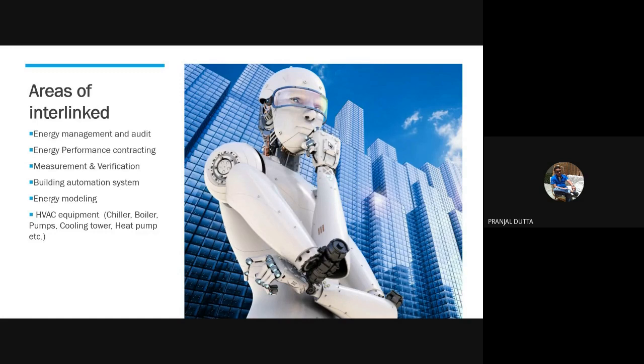That needs to be verified by someone M&V certified. Building automation is also very essential, because the entire software runs on data taken from the existing BMS—data for chillers, pumps, cooling towers, user sites, room temperature set points, flow, pressure, temperature, all coming from the building automation system. You need a fair idea of how equipment is connected, what data points are available, and what data is missing before moving to the next level of software implementation.